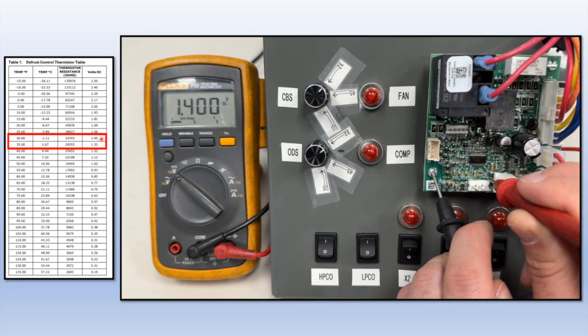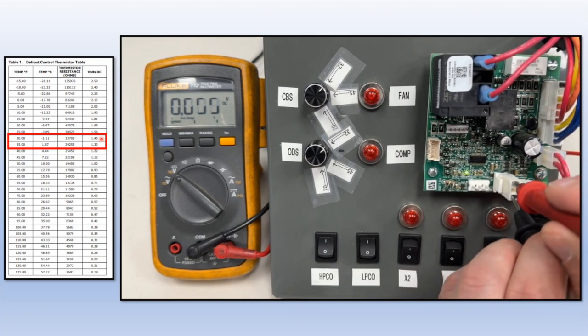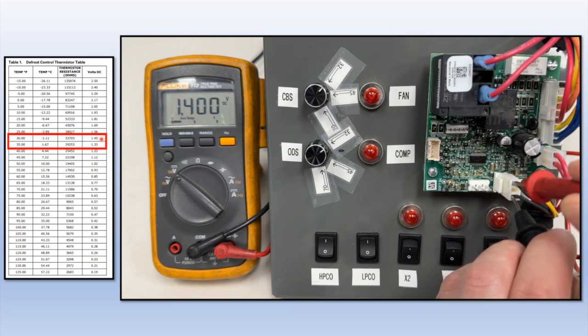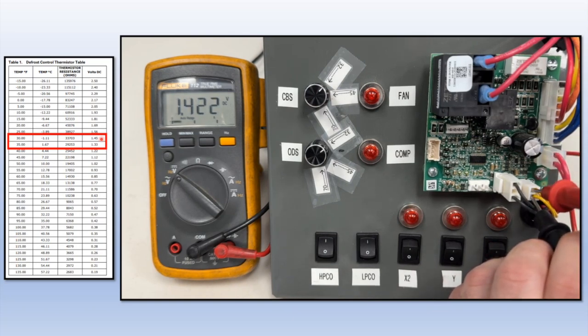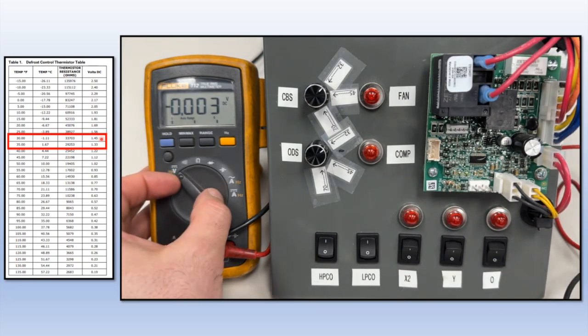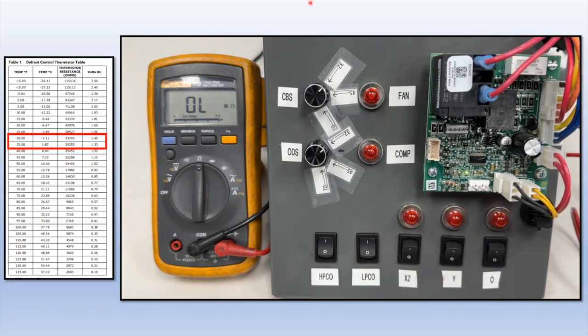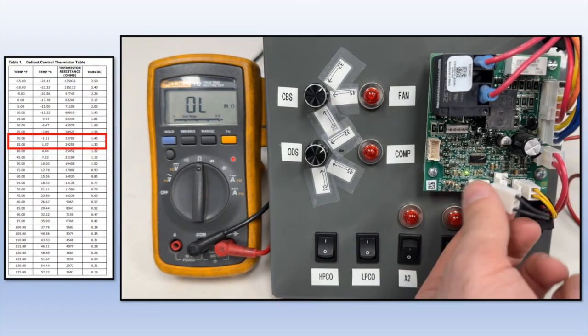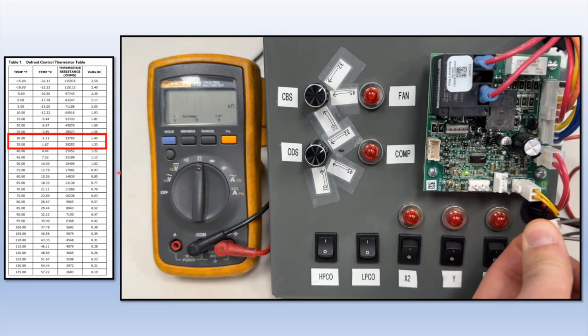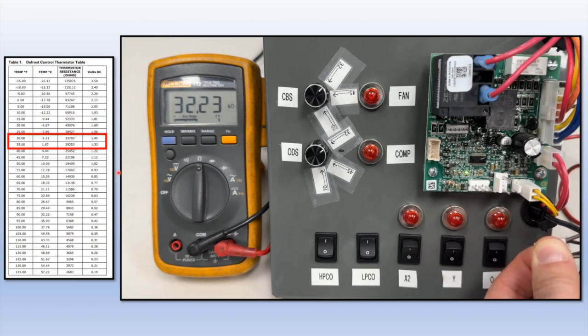So in this case, we verified that the source voltage is good from the board, and we also verified that if the correct voltage is coming back, then the resistance is also correct. We could do that same check by putting our leads at the back of the, in this case, the outdoor temperature sensor being black wires, 1.4 volts. Yellow wires being the coil bottom sensor, we have that same 1.422 volts. If the voltages were incorrect, we would switch to resistance, pull it off, and check the kiloohms through the sensor. In this case, we have 32.23 kiloohms. We would reference that chart to see if that's the right kiloohms for the temperature that it is.